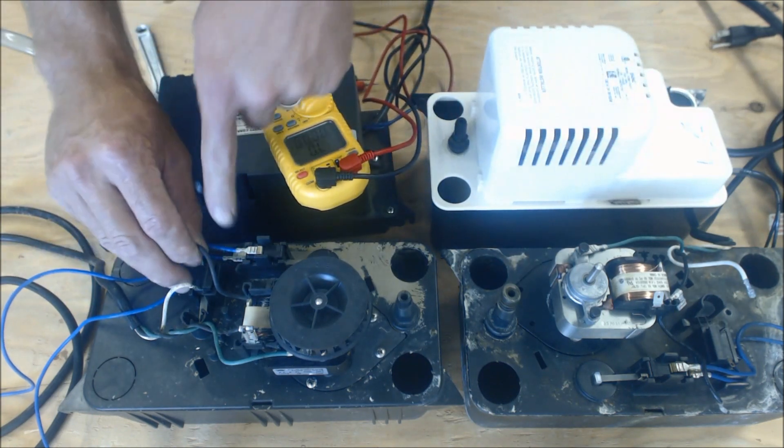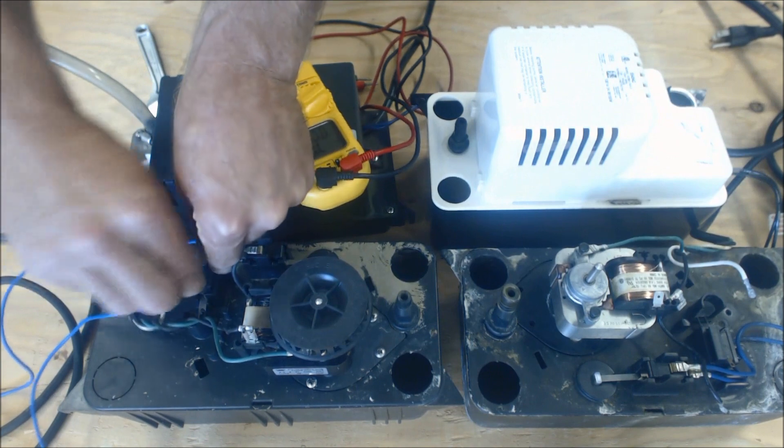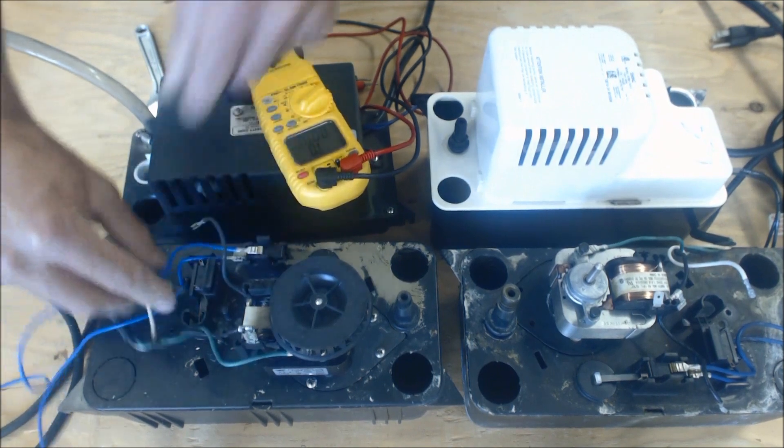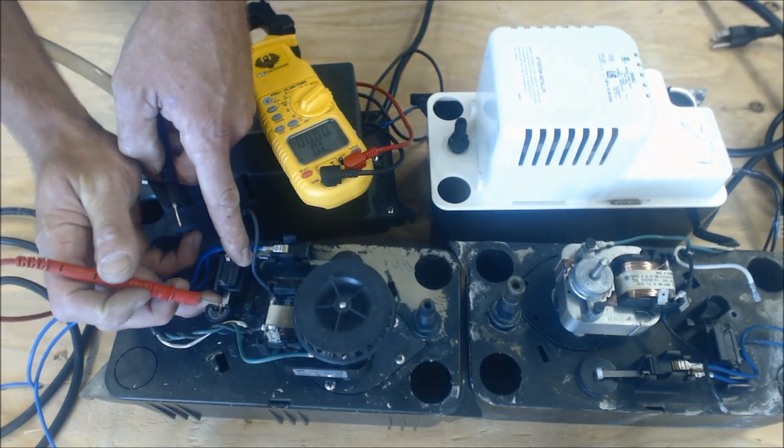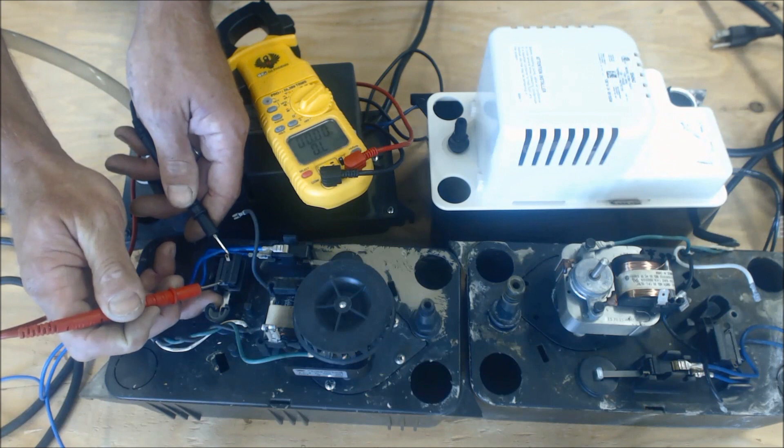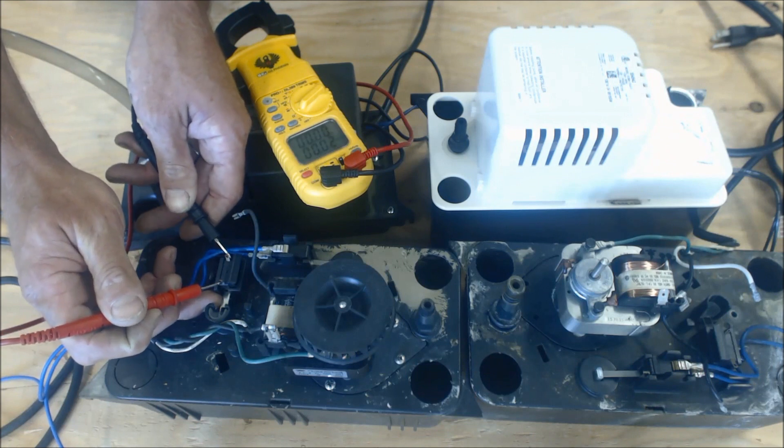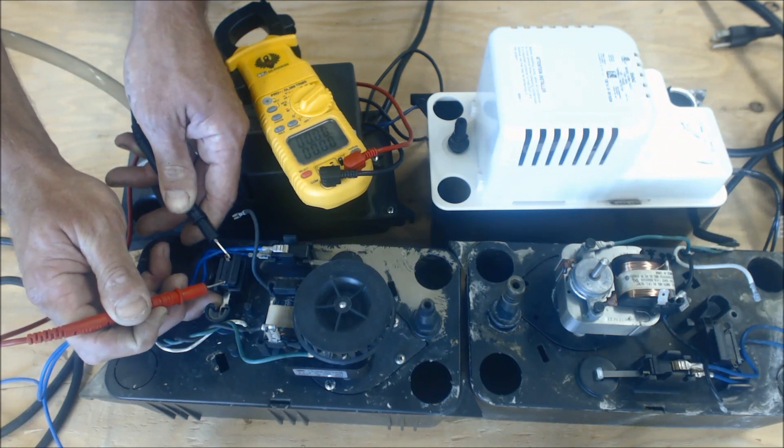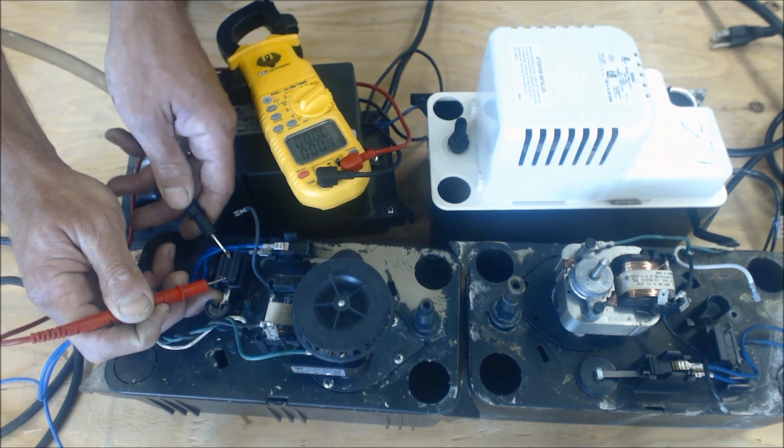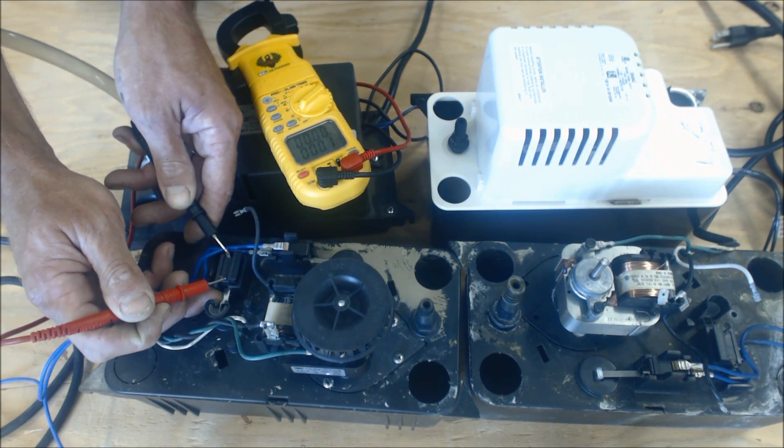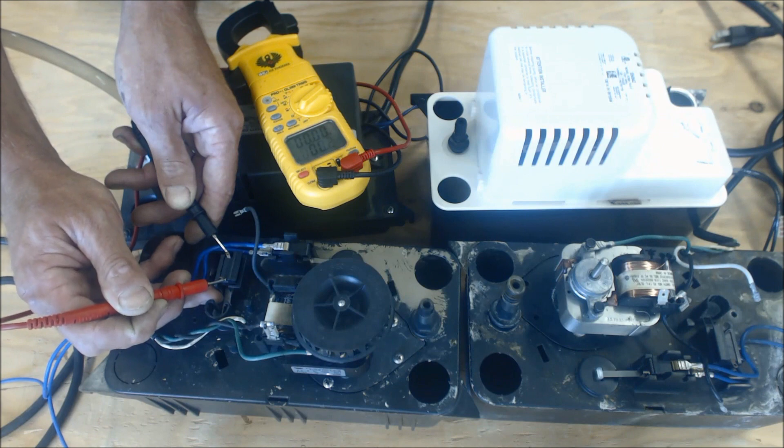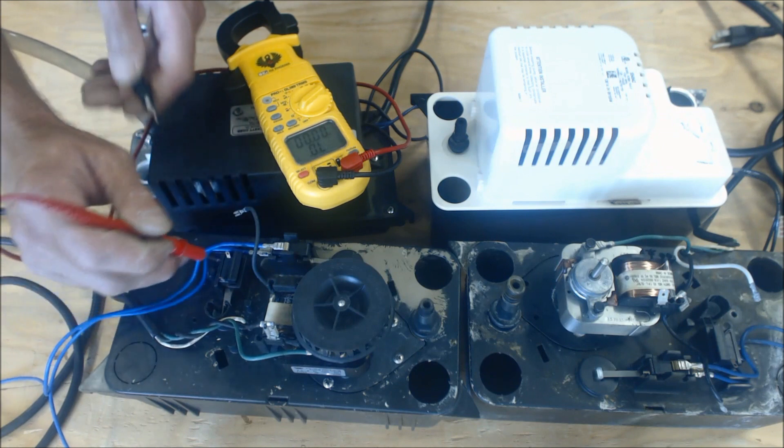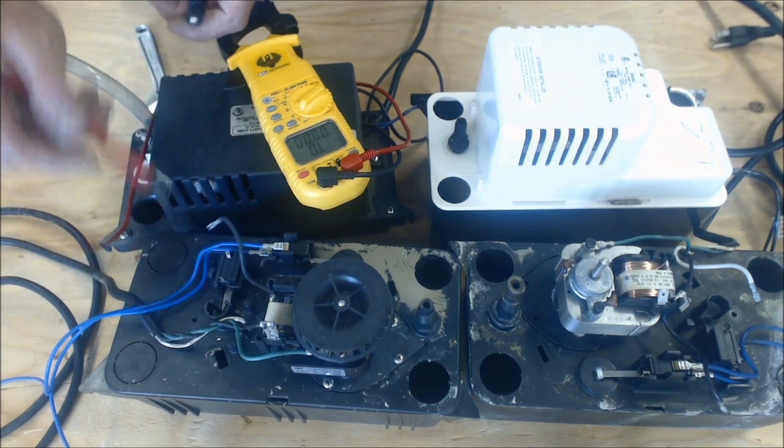So to check this micro switch right here, you can just go ahead and pull up on the float, and then you're just going to take a resistance reading. And right now we see 0.0 ohms of resistance. And then we would let it down, we read OL. So that switch is working properly.